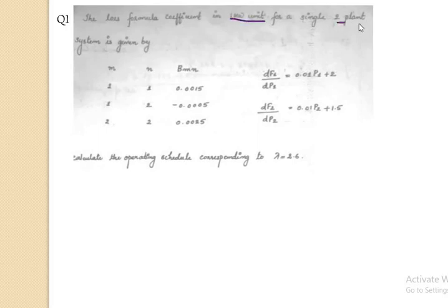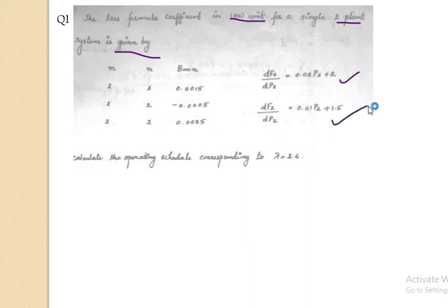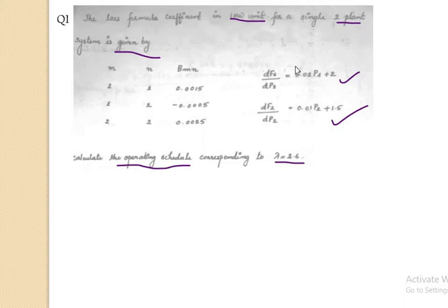Here is one question. The loss formula coefficients in 1 per megawatt units for a single two-plant system are given — M and N values, B_MN values are given. Then dF1/dP1, the incremental cost of the first unit, and dF2/dP2, the incremental cost of the second unit, are given. Calculate the operating schedule, meaning P1 and P2, corresponding to λ = 2.6. When B_MN coefficients are given, it is clear that transmission loss should be considered.